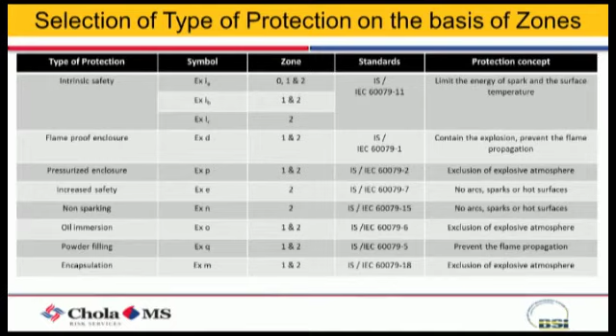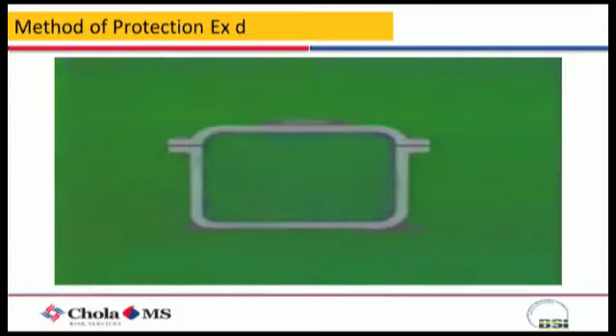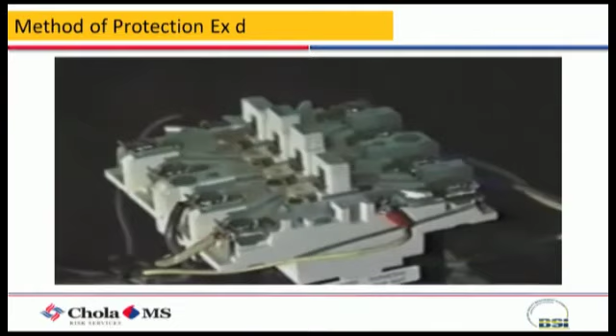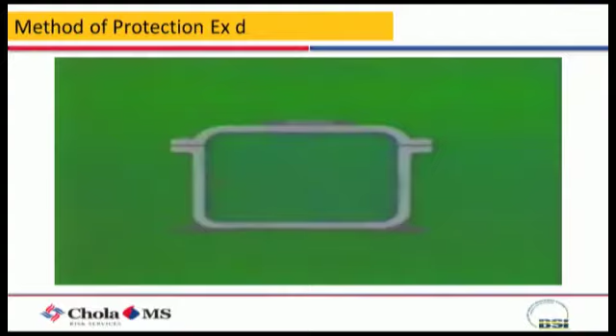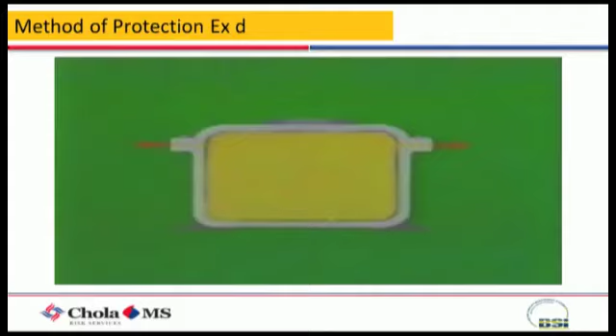This is a flame proof box. What happens is there is a mixture inside because it's in the process area, so the mixture vapors go inside and accumulate. When there is a spark occurring inside - every time you switch on and off, similar to an application at home - a spark is generated inside. Due to that, the entire box will explode internally, but it can withstand that explosion and finally send out only cool air, which is safer even in the surrounding. That's how flame proof equipment protects.